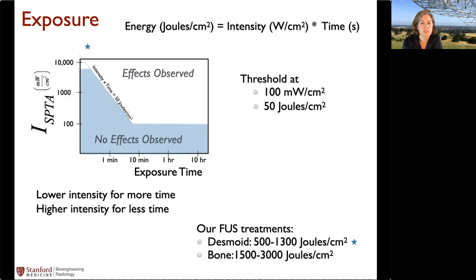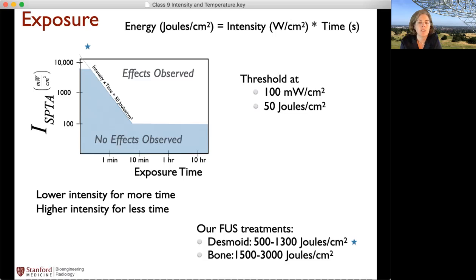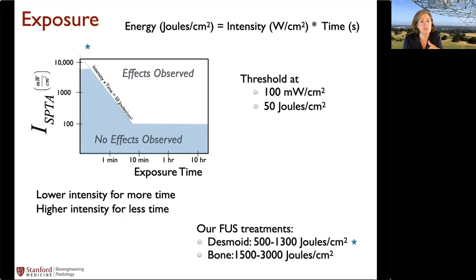And just to put this into perspective, when we're actually trying to heat the tissue, when we're treating desmoids, which are soft tissue tumors, it's not going through any bone, it's just going through soft tissue. We're trying to deliver at our target about 500 to 1300 joules per centimeter squared. So let's just look at the 500 joules per centimeter squared. We're talking about exposures that are way up here. So what we're saying is that these 50 joules per centimeter squared is much lower than what we're trying to do clinically. So this is what we need to be concerned with. But this does introduce the concept that it's not just a single threshold at an intensity level, but intensity and time both matter.